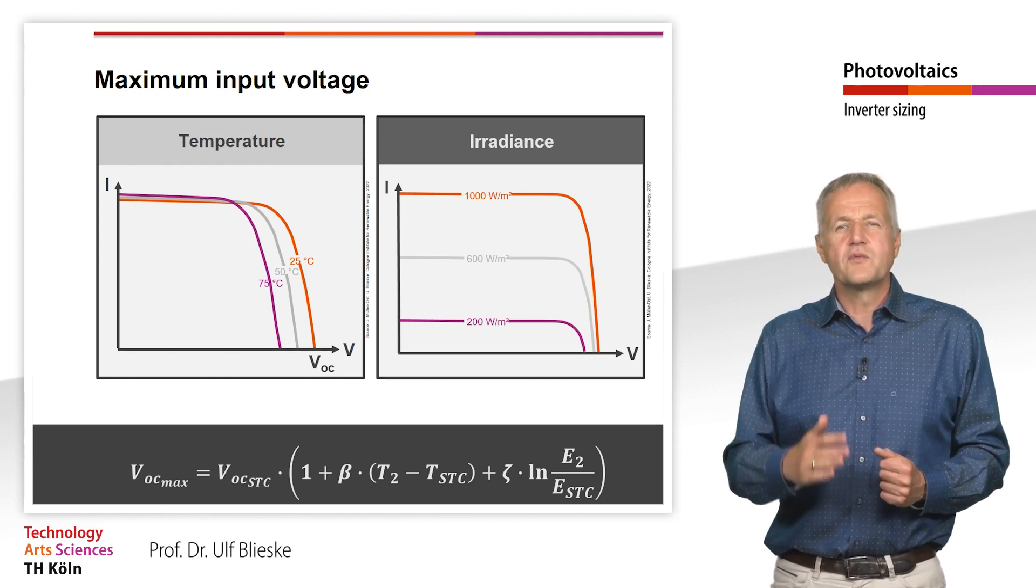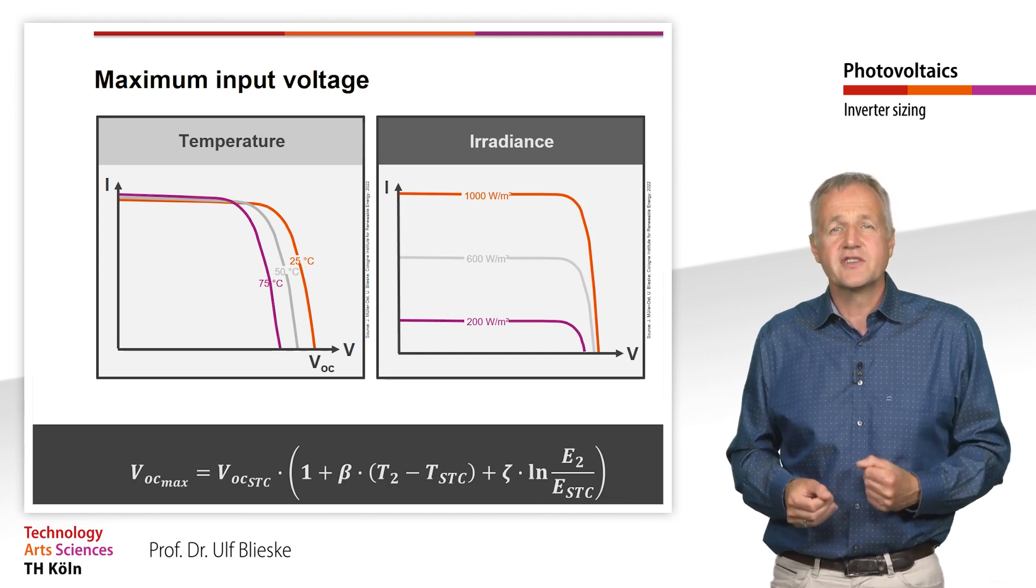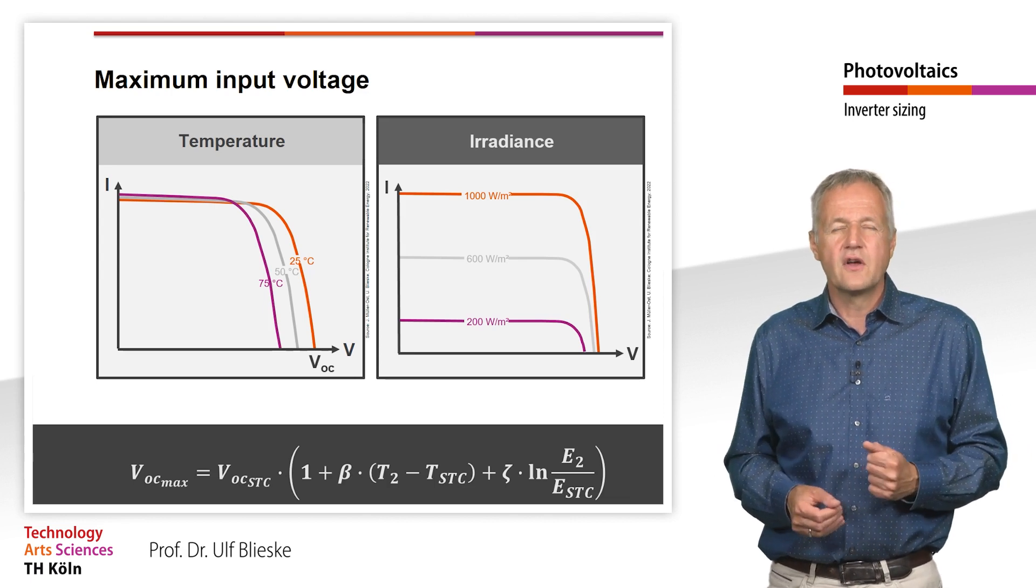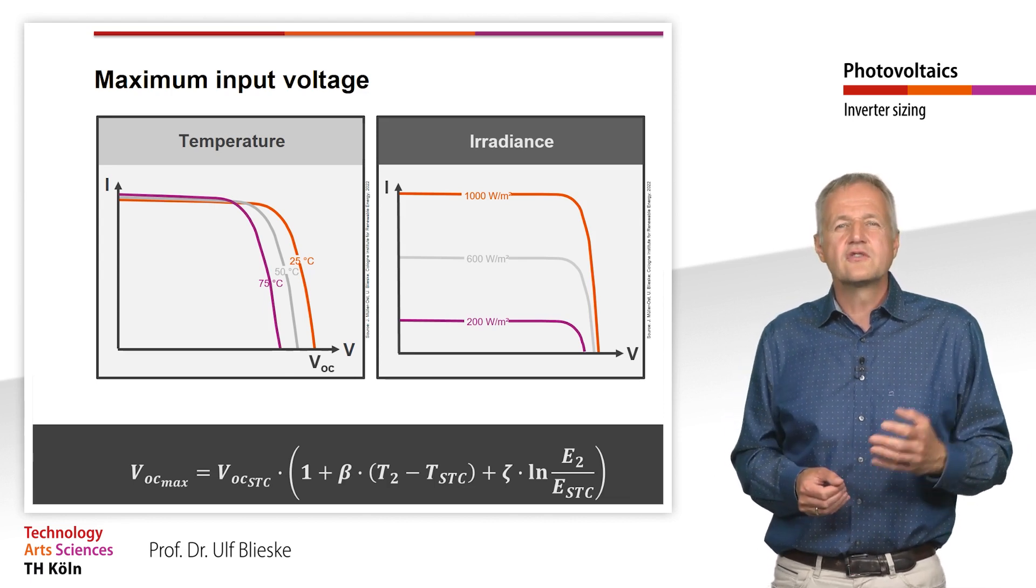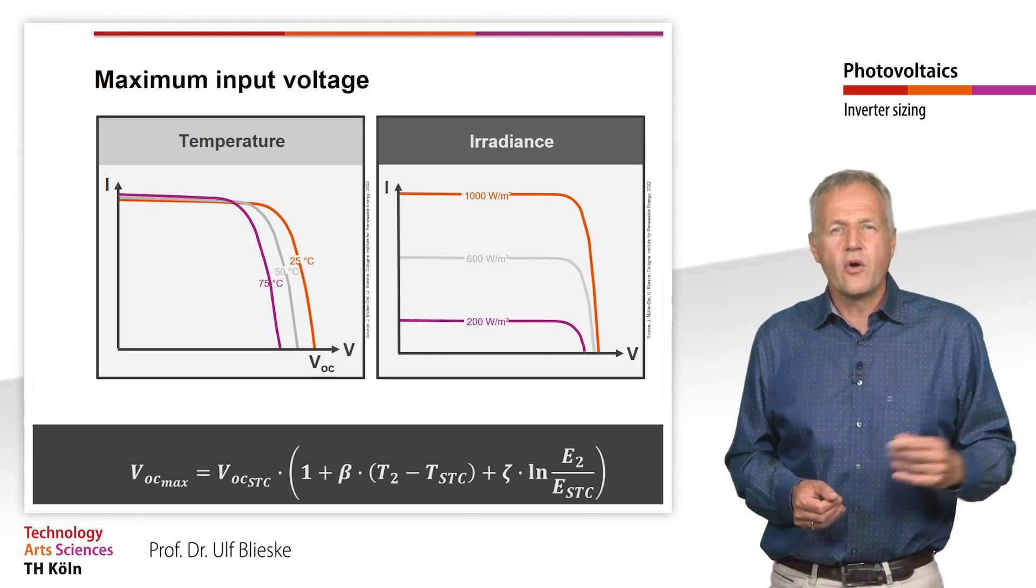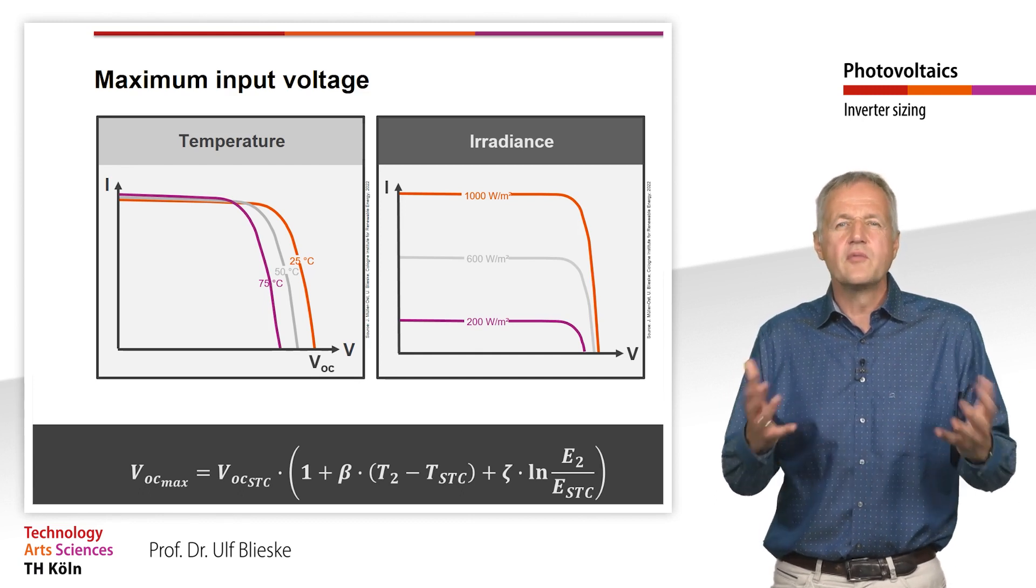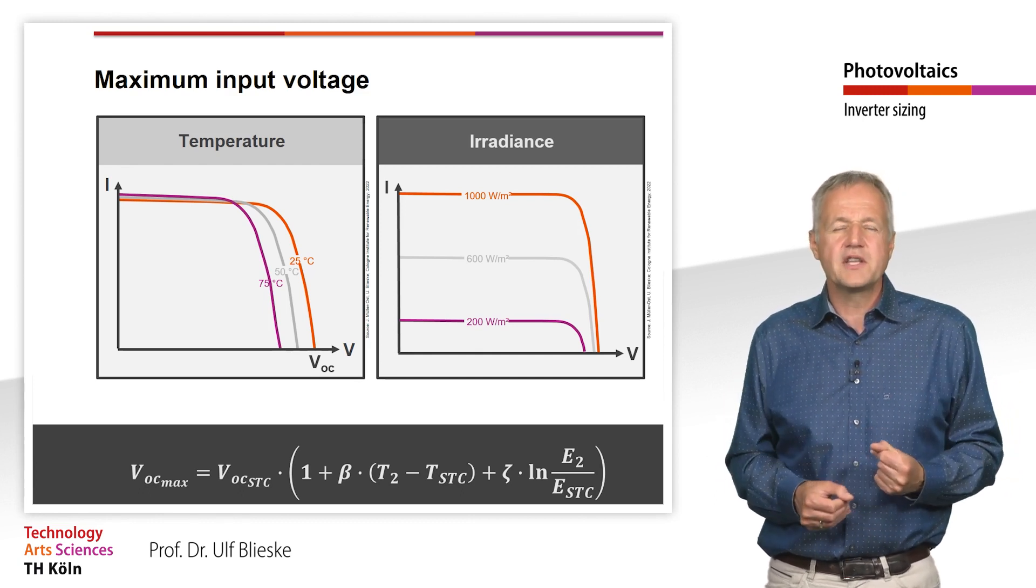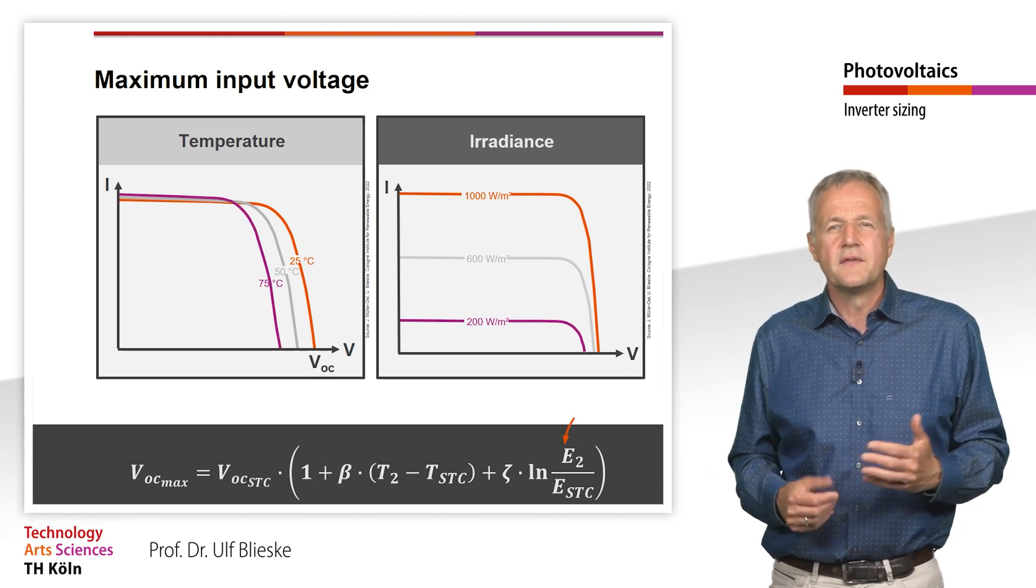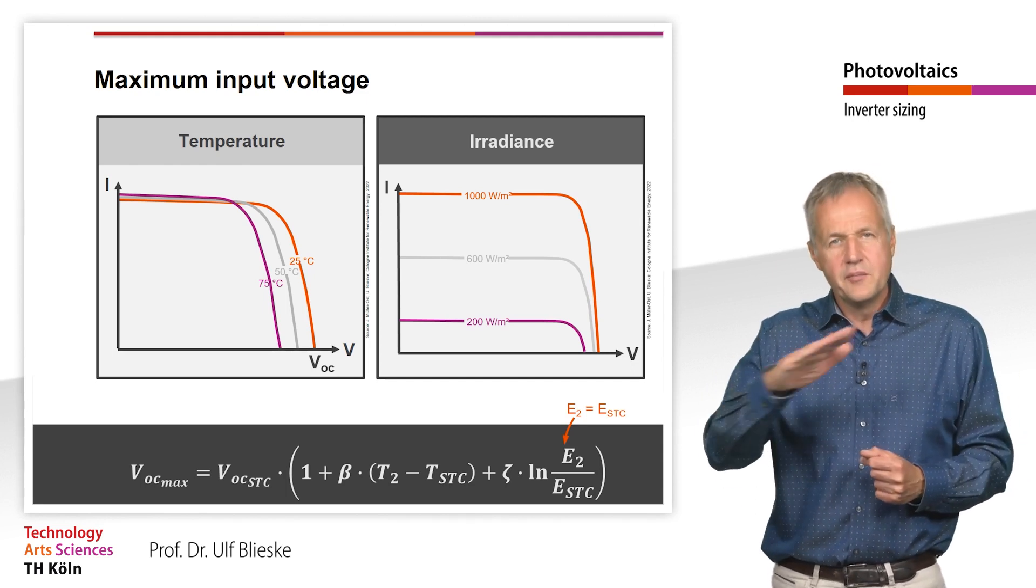This mainly depends on the location and the orientation and the inclination of the solar modules. If the modules are installed with a steep tilt angle, high irradiance at low temperature is definitely possible in winter with well back-ventilated modules. However, due to the logarithmic dependency, the irradiance has a much smaller overall effect on the voltage than the temperature. Thus, we assume an irradiance of 1000 W per square meter for the calculation of the highest open circuit voltage. In the equation for the open circuit voltage, the last term is therefore eliminated.